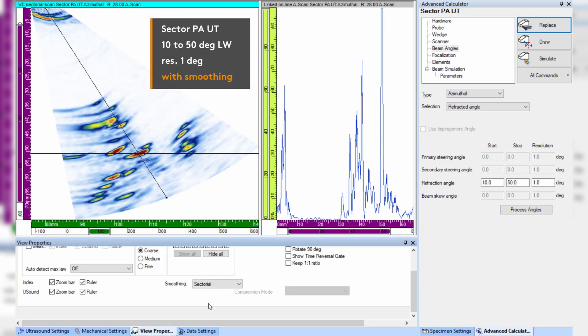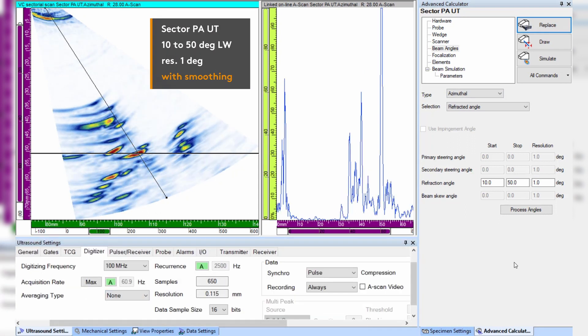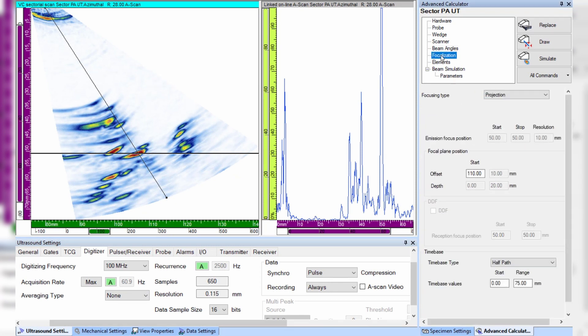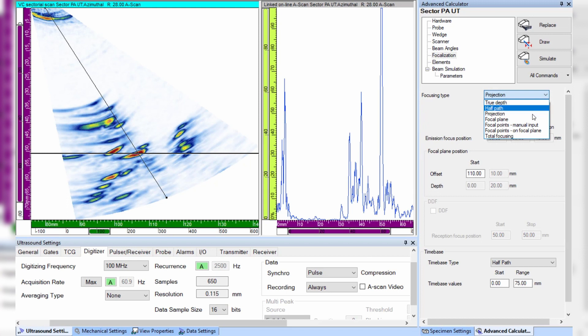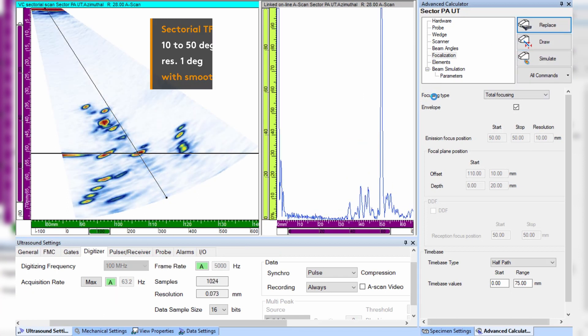And to improve the focusing capability, let us activate sectorial total focusing in the advanced calculator. This algorithm uses the elementary A-scans from an FMC firing sequence to generate the sectorial sweep, very similar to standard phase array but focused in each point along the sound path of each angle.